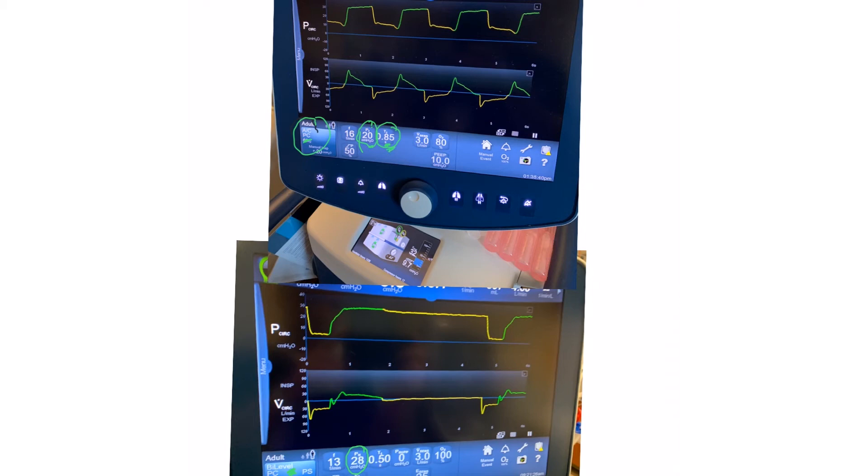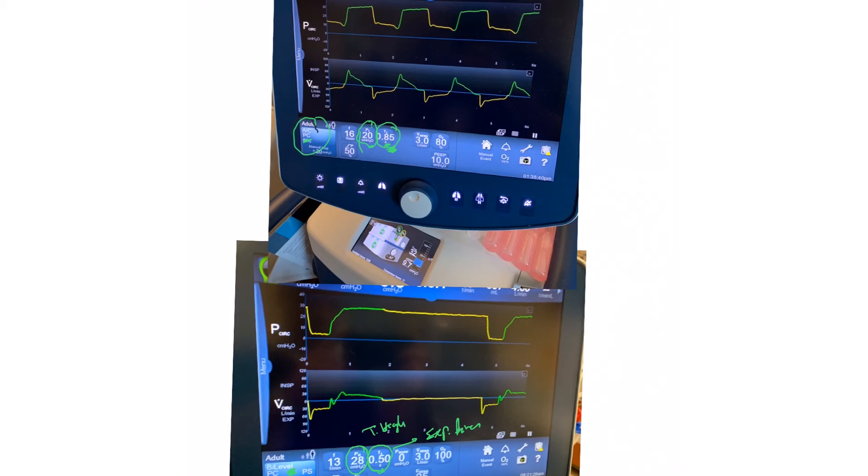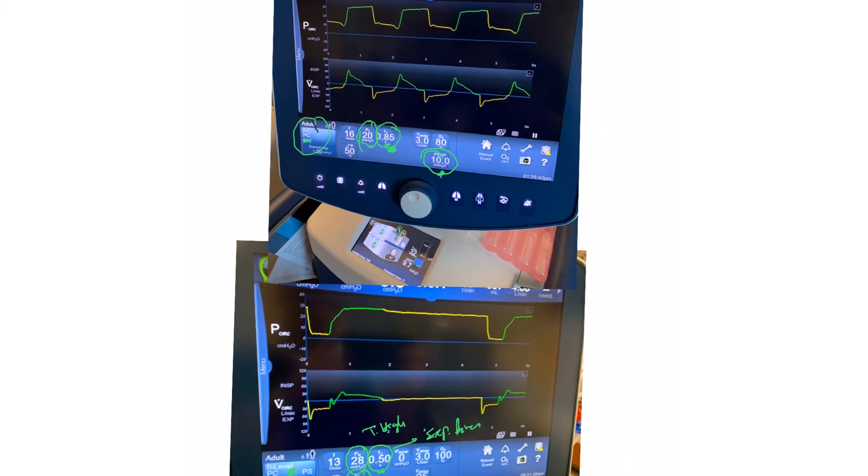The inspiratory time is called T high now. It's not displayed here because we have T low, which is the expiratory time, and the inspiratory time is calculated indirectly. We'll show you that in a second. Simply just changing the terms, right? The P here, we change the term to P low—pressure low. So it's similar to the PEEP. Now we call it P low.